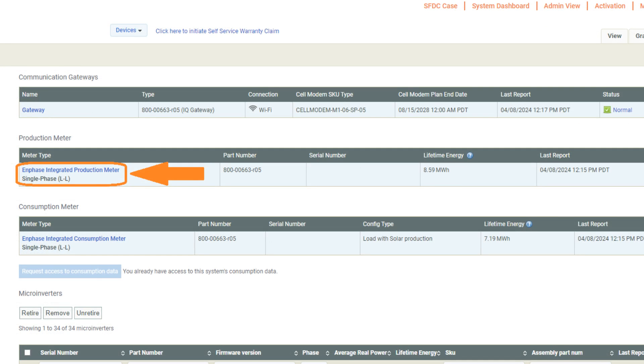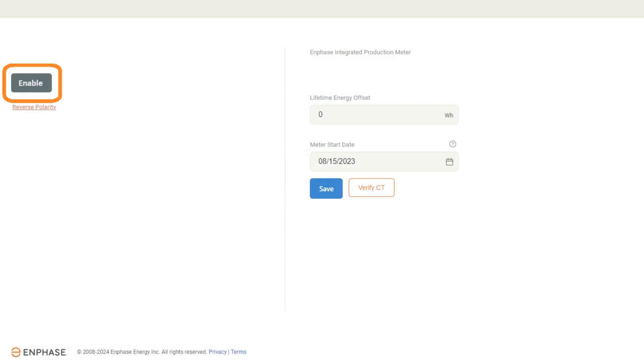If the production meter is not enabled, select the Enphase integrated production meter by clicking on the blue hyperlink. Here you will see the option to enable the CT. After selecting Enable, be sure to click the Save button.